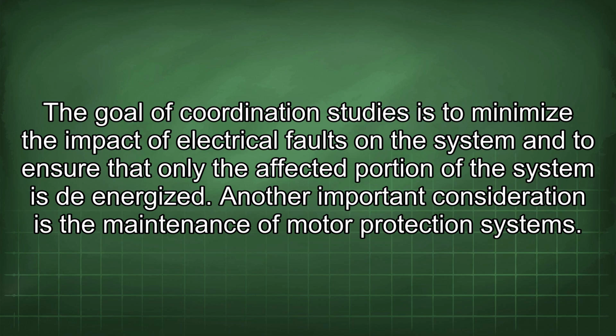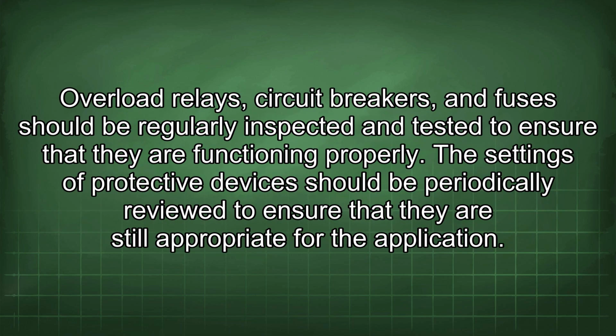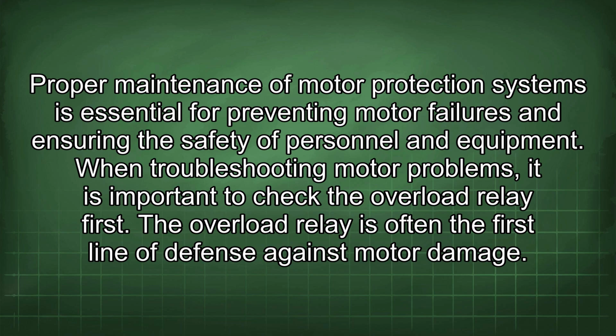Another important consideration is the maintenance of motor protection systems. Overload relays, circuit breakers, and fuses should be regularly inspected and tested to ensure that they are functioning properly. The settings of protective devices should be periodically reviewed to ensure that they are still appropriate for the application. Proper maintenance of motor protection systems is essential for preventing motor failures and ensuring the safety of personnel and equipment.